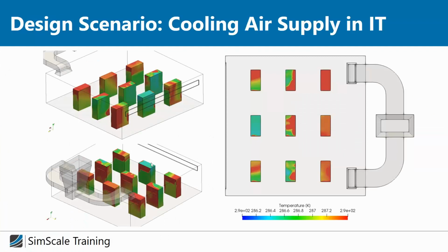And so I just prepared some of these images. And here you can see the initial design of our server room. In the picture, the color represents the surface temperature on the server racks. You can see that we have a lot of hot spots, especially on the side which is more away from the cool air. Especially here you can see these very hot areas, and all in all it does not look very equally distributed.